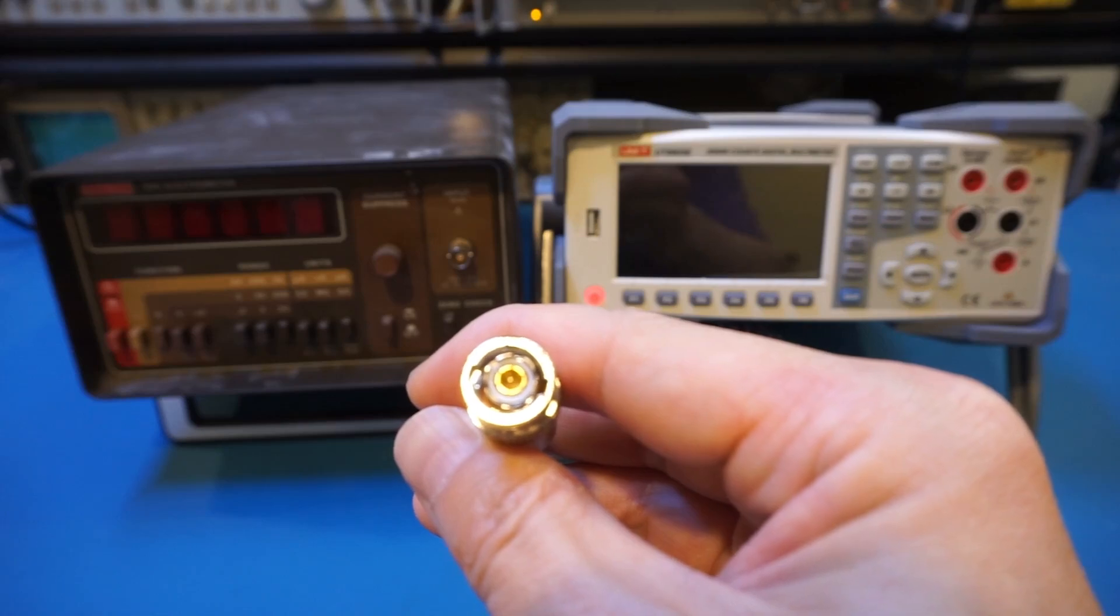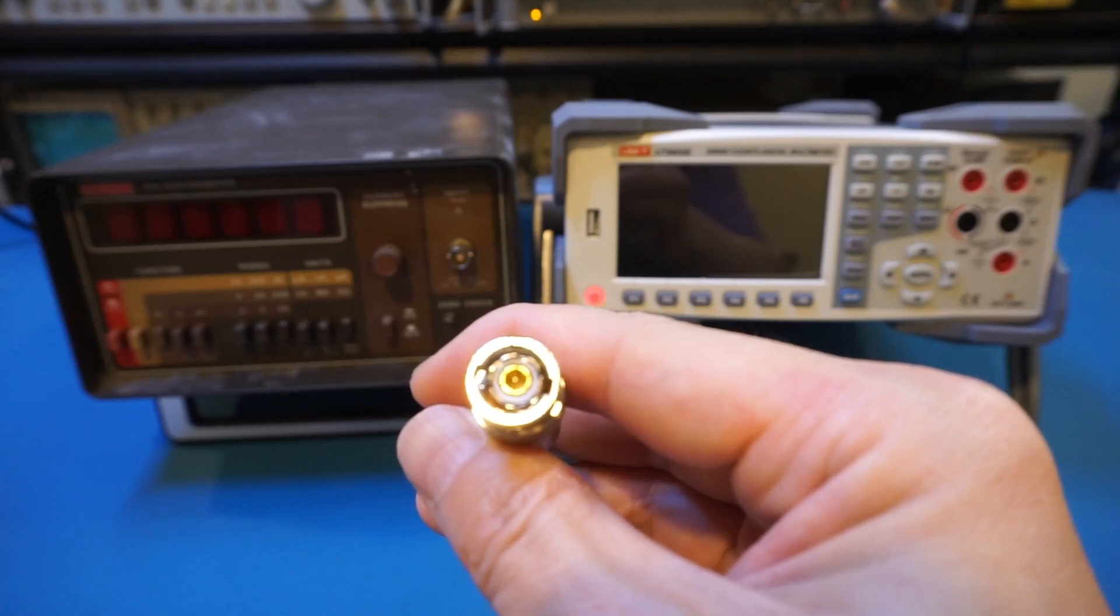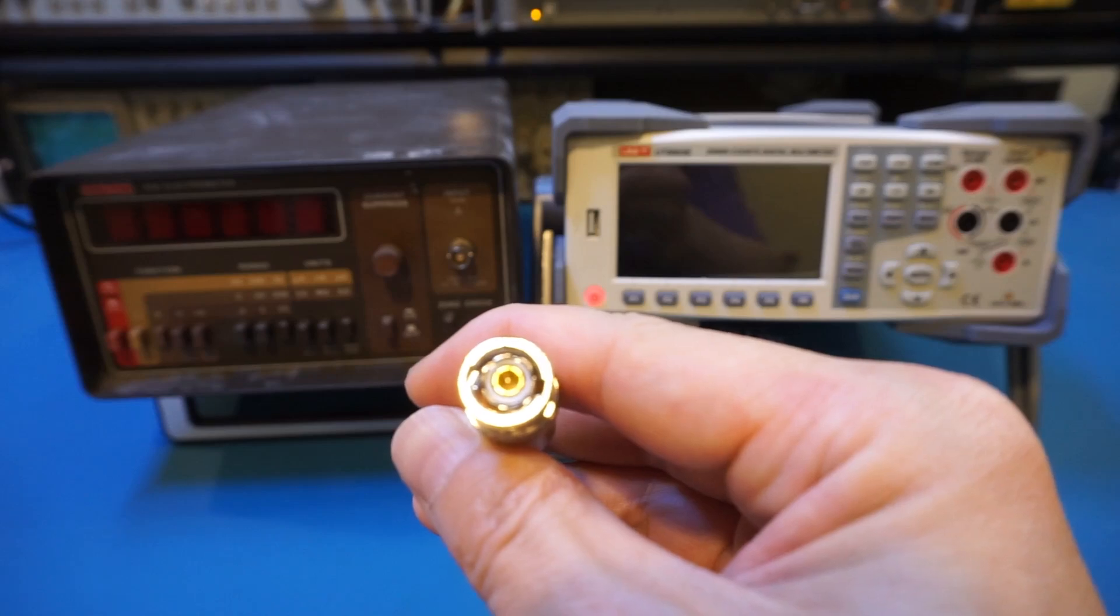The guard is driven to the same potential as the center conductor of the cable, which is where the red alligator clip is connected to. So this eliminates the current leakage to the ground, and also removes parasitic capacitance due to charging and discharging.